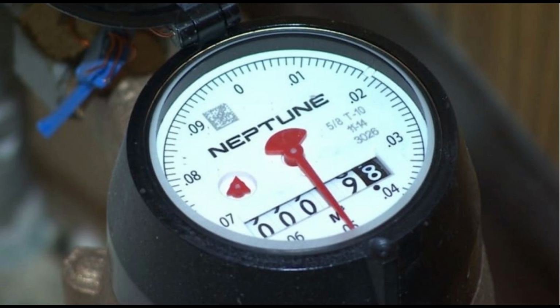Magnetic flow meters, commonly referred to as mag meters, are technically a velocity-type water meter, except that they use electromagnetic properties to determine the water flow velocity, rather than the mechanical means used by jet and turbine meters. Mag meters use the physics principle of Faraday's law of induction for measurement and require AC or DC electricity from a power line or battery to operate the electromagnets. Since mag meters have no mechanical measuring element, they normally have the advantage of being able to measure flow in either direction, and use electronics for measuring and totalizing the flow.